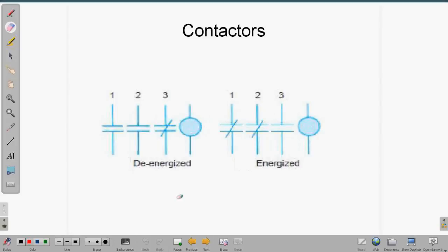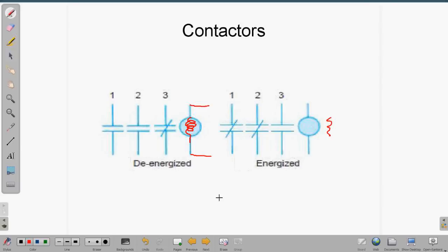Here's an example of a de-energized state with no power applied. This is our coil, which creates the magnetic field that switches the contacts. With no power applied, terminal three is normally closed, and one and two are normally open. When we apply power, the normally closed number three contact opens, and the two normally open contacts, one and two, close. You can do quite a bit of switching with relays if you understand and know how to wire them.